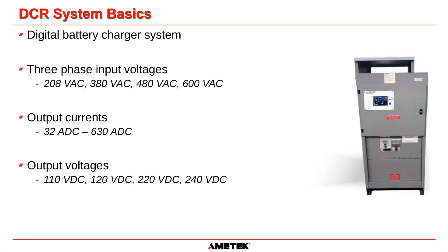So the basics of our DCR, it's a digital battery charger system. We accept three-phase input voltages of 208, 380, 480, and 600 volts. And we have a range of currents starting at 32 amps up to 630 amps. And output voltages are 110 volts DC, 120, 220, and 240. And we can also customize pretty much anything. So if you need a different voltage or different current, we can probably accommodate that as well.